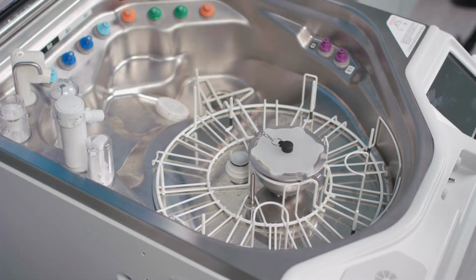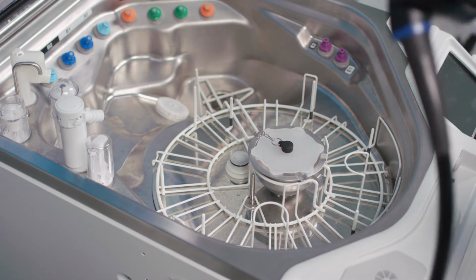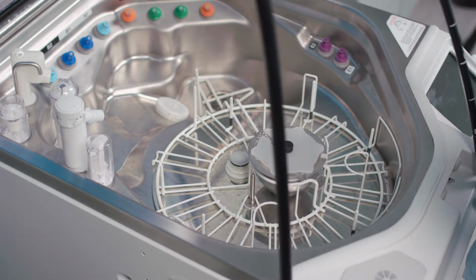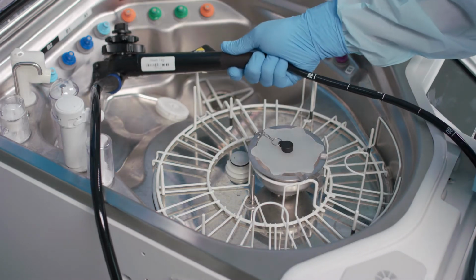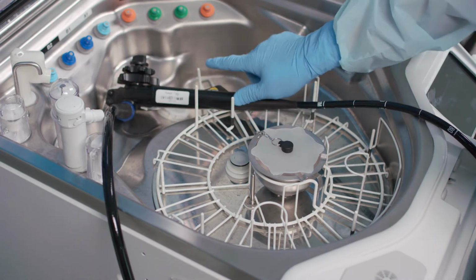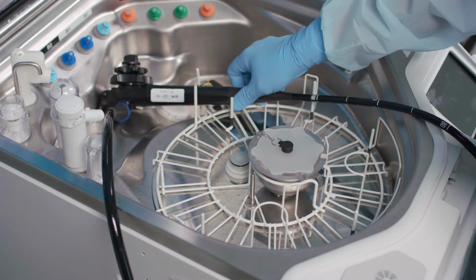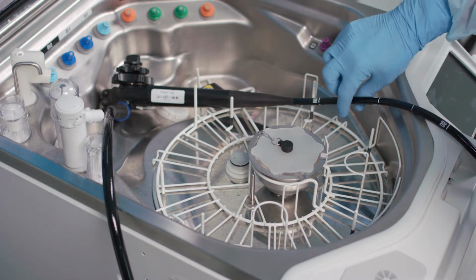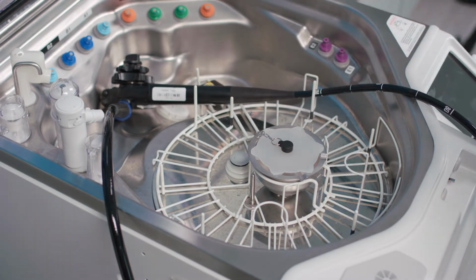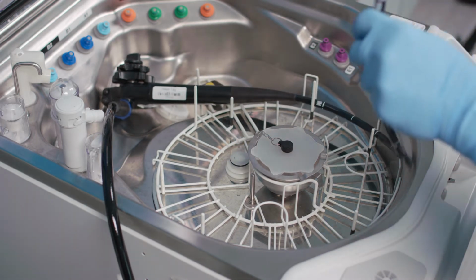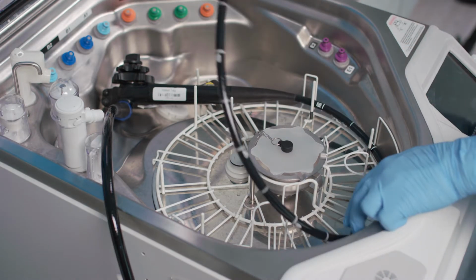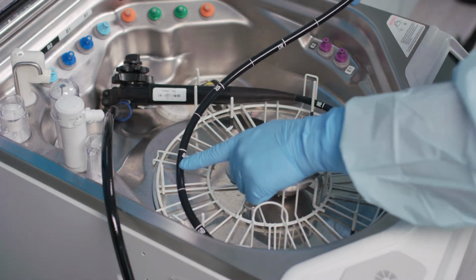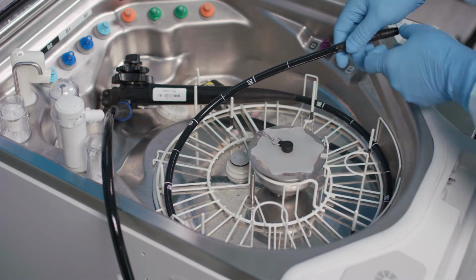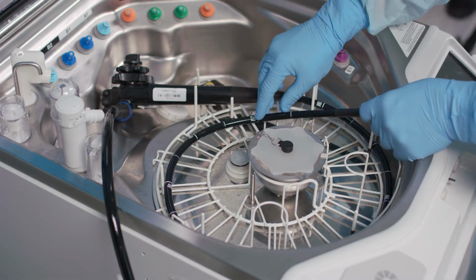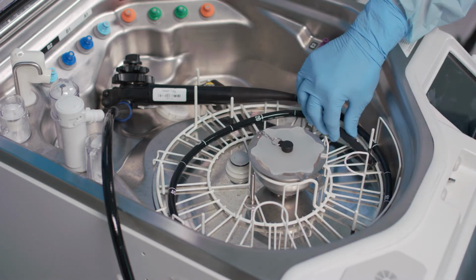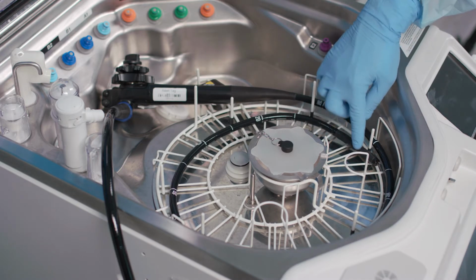Now that the retaining rack is installed and the accessories are removed from the endoscope, let's begin loading the scope. First, set the control section to the left of the index pin. This is located at the deepest part of the reprocessing basin. Then, we're going to wrap the insertion tube clockwise around the retaining rack from the outside of the retaining rack moving toward the inside. Make sure that the insertion tube's distal end is placed within the retaining rack.